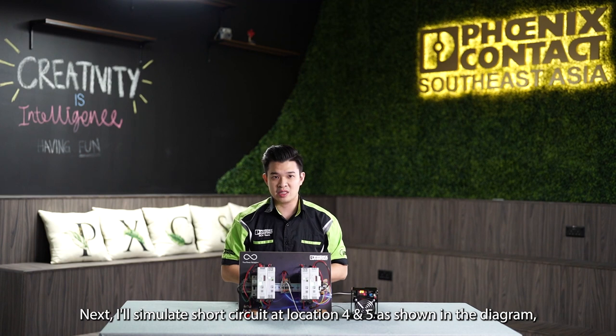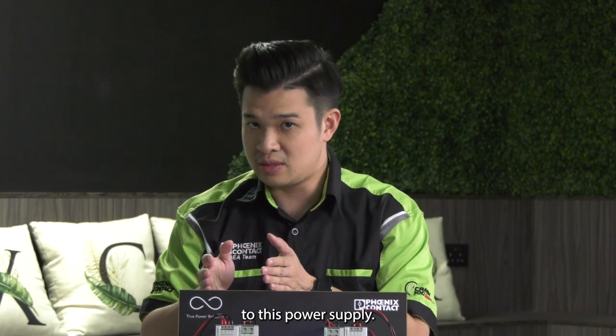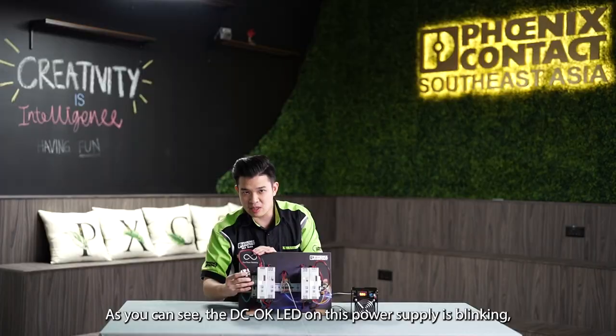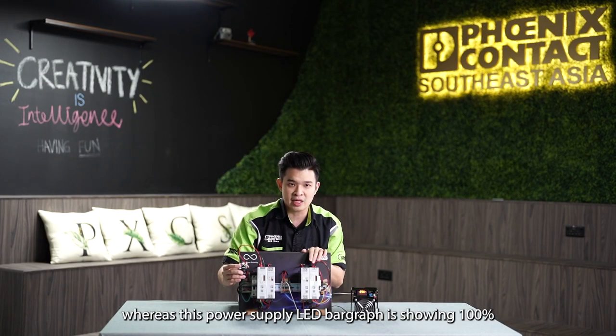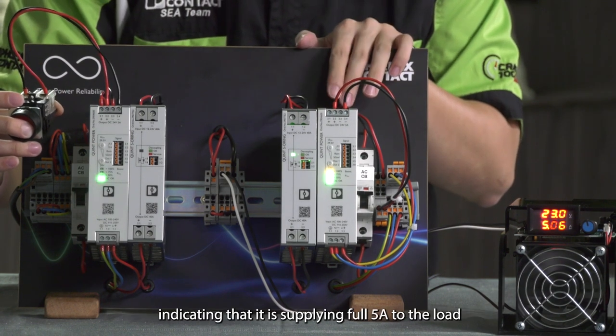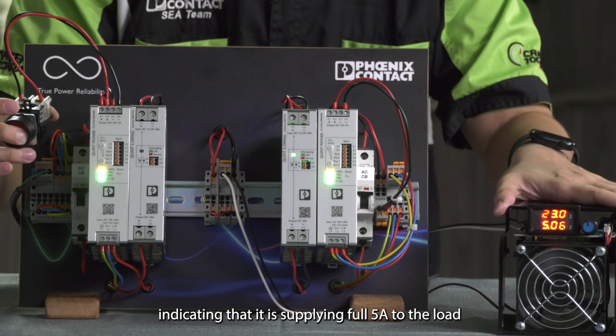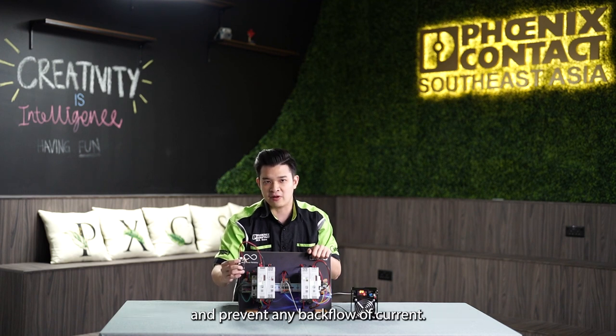Next, I will simulate a short circuit at locations 4 and 5 as shown in the diagram on this power supply. As you can see, the DC OK LED on this power supply is blinking, whereas the LED bar graph is showing 100%, indicating that the other power supply is supplying the full 5A to the adjustable load without any interruption. With our Quint 4 ORING, it can isolate one power supply from another during a short circuit and prevent any backflow of current.